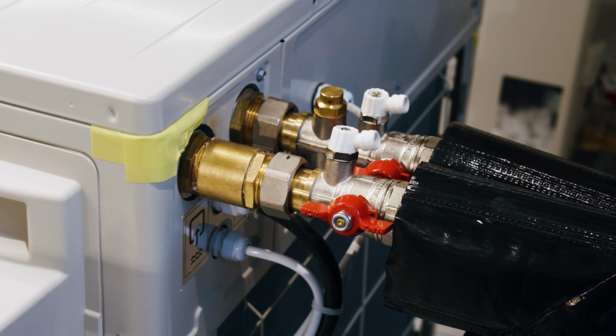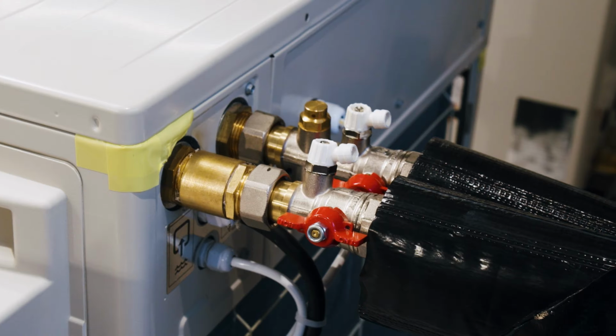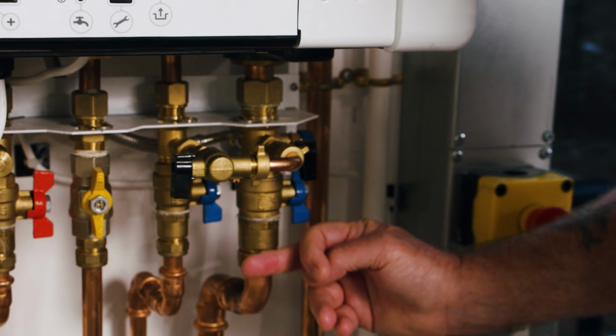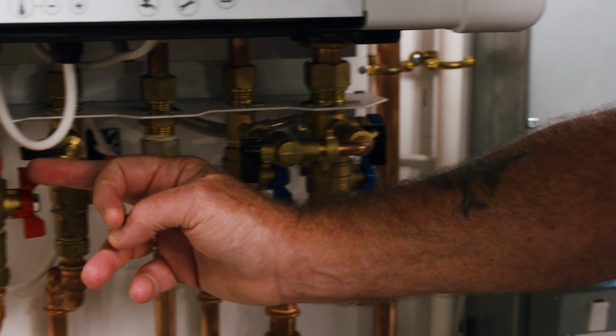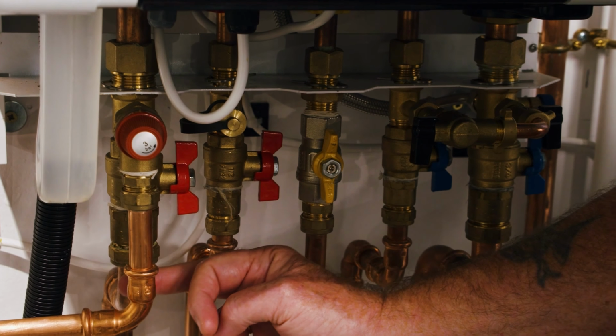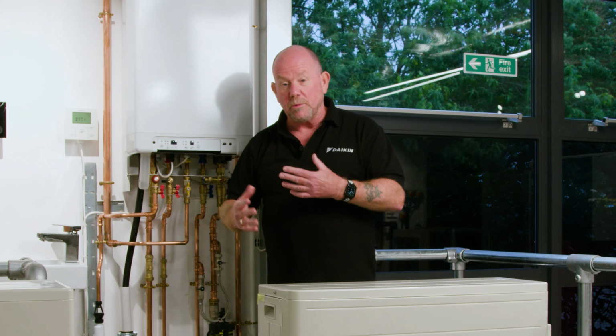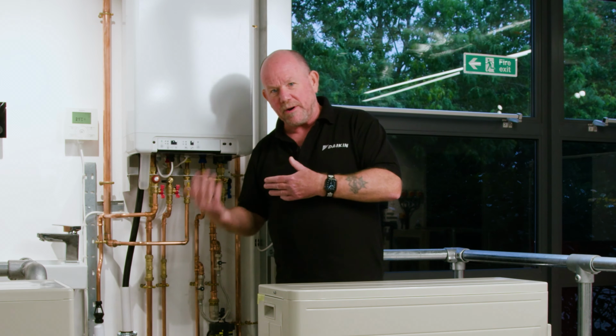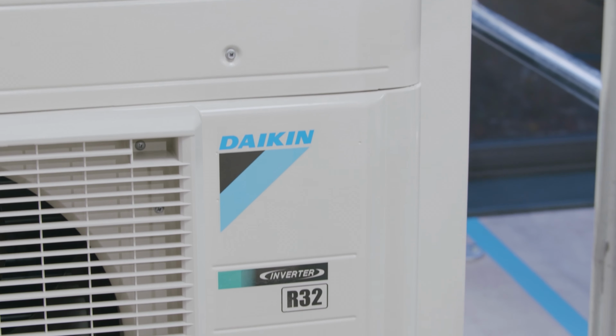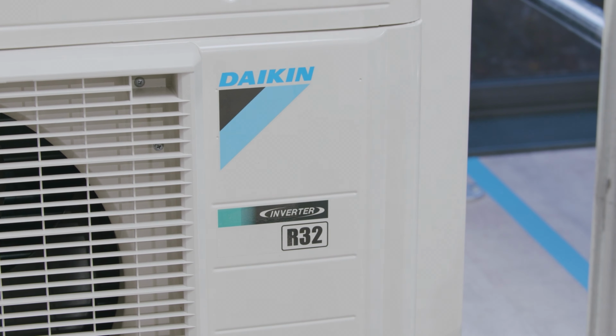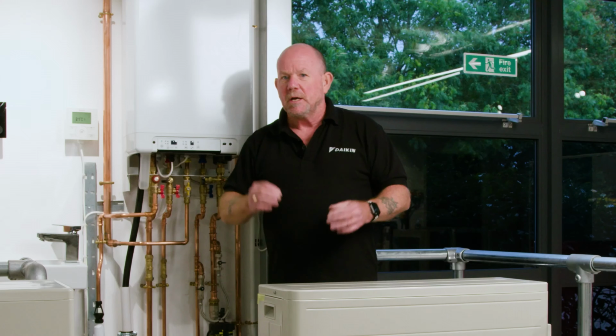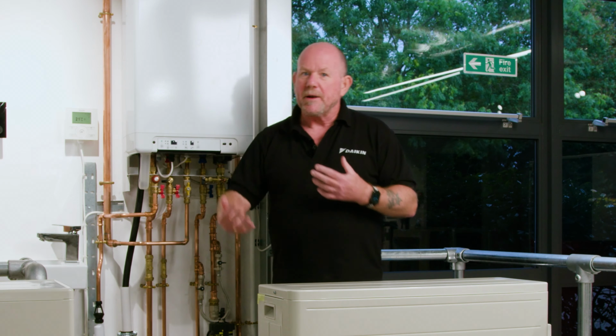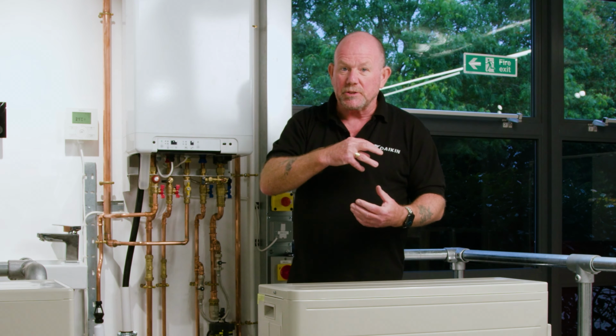Just to put a little bit more meat on that bone, we go from the flow connection on the outdoor unit to the return connection on the boiler. We pass through the boiler, out the flow connection of the boiler, to our heating system, or if we've got stored hot water, to either our heating or our hot water cylinder, and then we return back to the outdoor unit. So I guess the easiest way of thinking of it is that the boiler is in series with the outdoor unit.